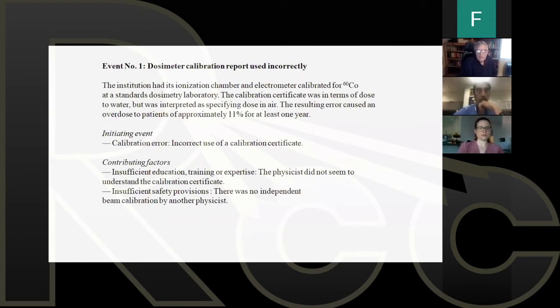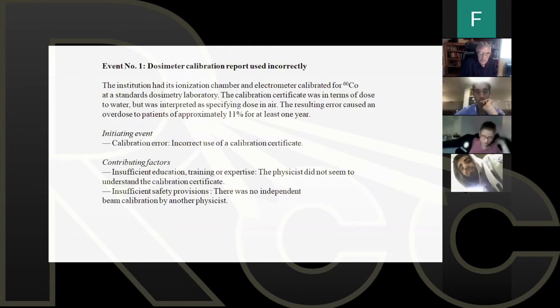The standard for instrument calibration is cobalt-60, and it's done in a standard calibration laboratory. There are many throughout the country and the world. The calibration certificate was in terms of dose to water. This is very much the current way of doing things. Your instrument is calibrated in terms of centigray delivered to water. However, the physicist, for some unknown reason, interpreted the result as specifying dose in air. And as you can imagine, because of the conversion factors from air to water, the resulting error overdosed patients by 11% for at least a whole year.